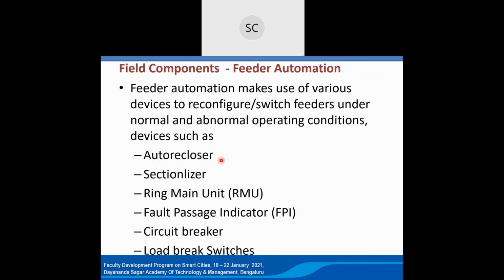Generally, auto reclosers will be just after the substations for overhead lines. It will be on the 11 kV side, and generally connecting this auto recloser immediately after the substation is not feasible, because the basic purpose of the auto recloser is to protect your substation breakers. Any time a station breaker trips, a very large number of customers get affected, and there will be more stress on the station breakers. So generally this auto recloser element will be installed on an overhead line strategically slightly away from the substation, where faults happen very frequently due to temporary causes like trees. So that is the strategic place for locating an auto recloser.